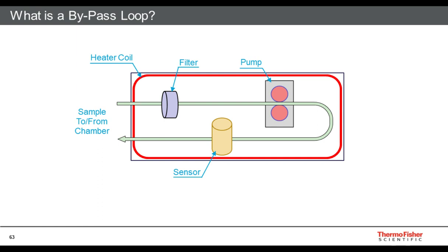So why would somebody offer this in an incubator? If you think about what's going on in the incubator chamber from an electronics perspective, not only is the chamber heated to 37 degrees, and not only is it very humid, and both of those things are very hard on electronics, but the CO2 gas provides an atmosphere that is weakly acidic due to carbonic acid. That's very detrimental to electronics. So if you put the sensor outside of that carbon dioxide gas and outside of that high humidity, it helps preserve the life of the sensor.